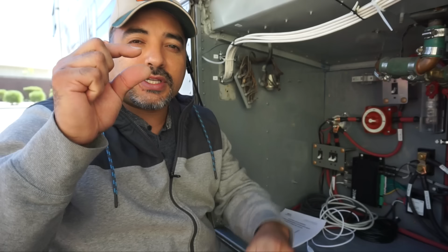a lithium system tends to have a very constant voltage, unlike a 12 volt lead acid system, which more or less declines linearly. So with lead acid you can use the voltage to estimate the state of charge. On a lithium, the graph flattens out for a long time, then falls off extremely rapidly. So just by knowing the voltage, you have no idea what the state of charge is - you don't know if you have 70% or 30% capacity, because the voltages are so close.